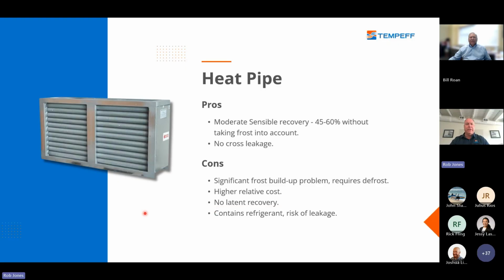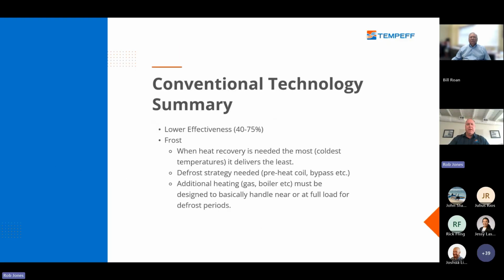Not very common anymore is the heat pipe style. We've seen these in operating rooms and clean rooms. They have moderate sensible recovery of 45 to 60%. They have no cross leakage, and that's why they're used in clean rooms. The cons of them: significant frost buildup problem, absolutely requires a defrost strategy, a higher relative cost, and no latent recovery. It also contains a refrigerant, so there is a risk of a leak.